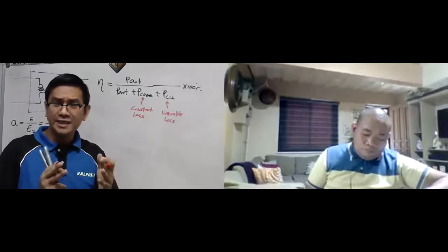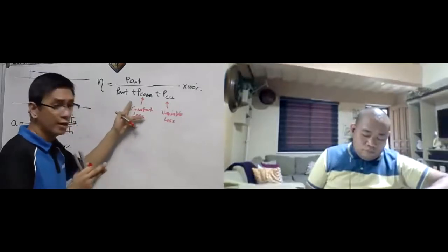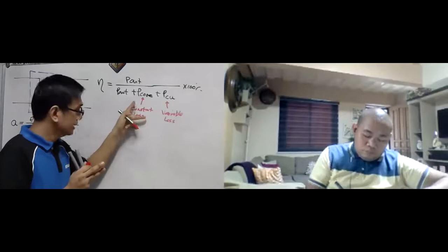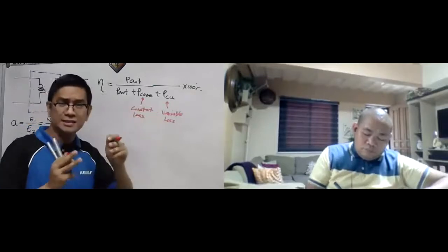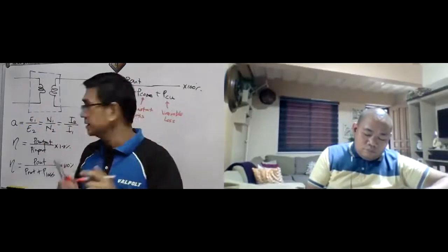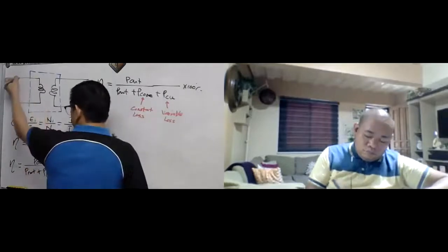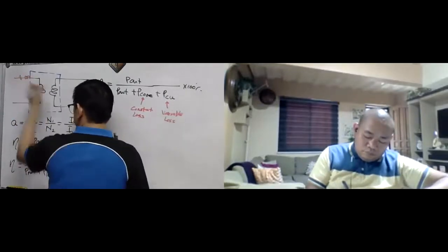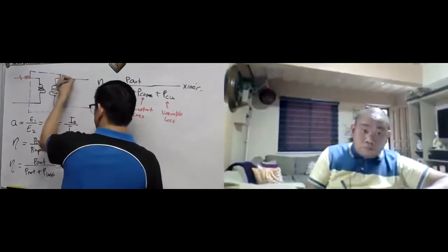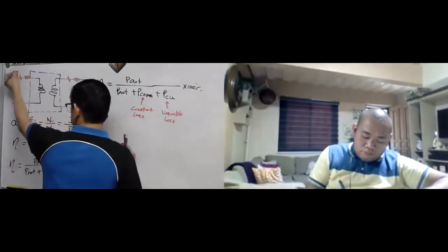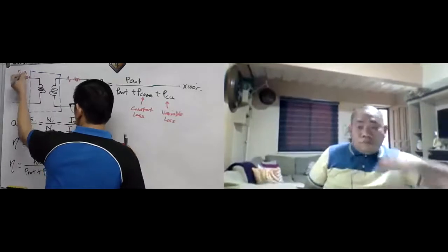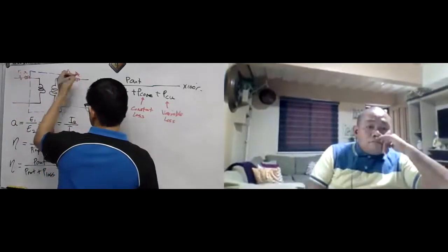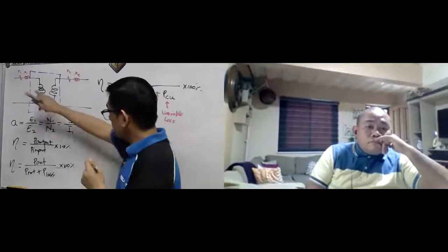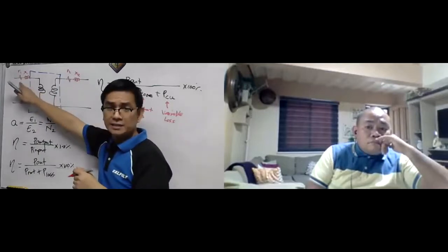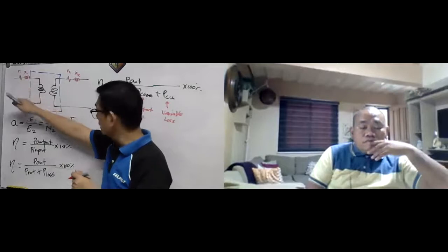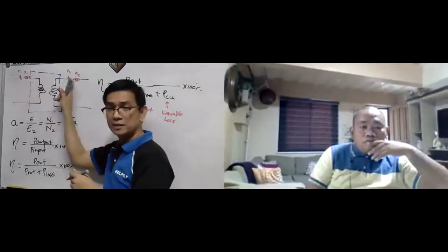What is a copper loss? Since the core loss is a constant loss in a transformer, what is a copper loss? A copper loss is losses in the wire. Remember that a transformer has a winding, let's say this is R1, X1, this is R2, X2. There are losses in the copper, which is I squared R, losses in the resistance for the primary and secondary.